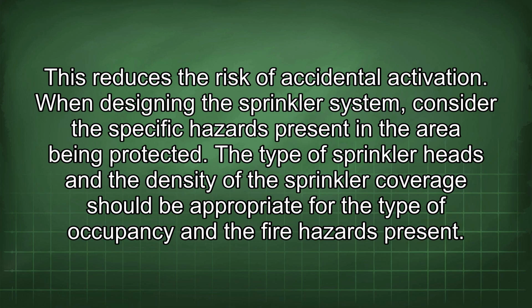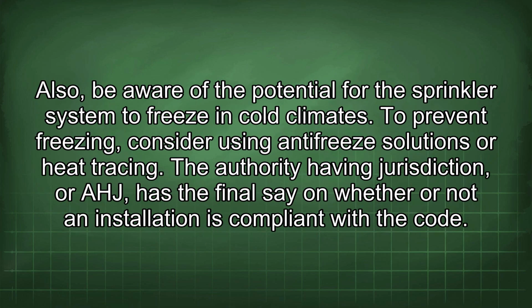When designing the sprinkler system, consider the specific hazards present in the area being protected. The type of sprinkler heads and the density of the sprinkler coverage should be appropriate for the type of occupancy and the fire hazard present. Also, be aware of the potential for the sprinkler system to freeze in cold climates. To prevent freezing, consider using antifreeze solutions or heat tracing.